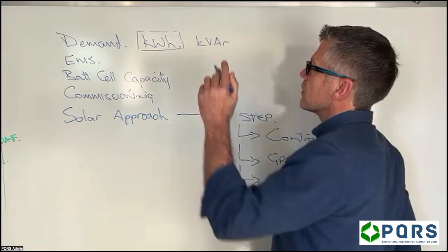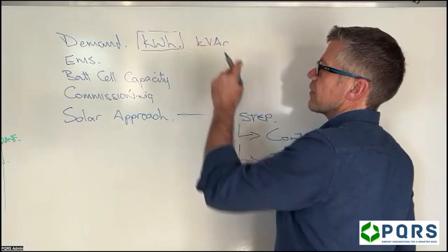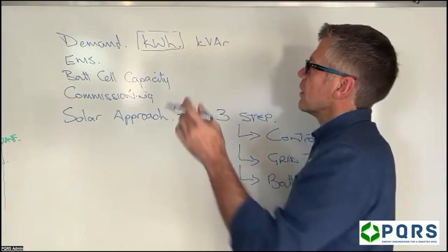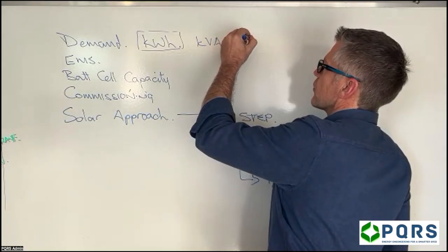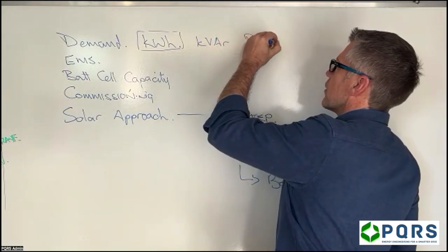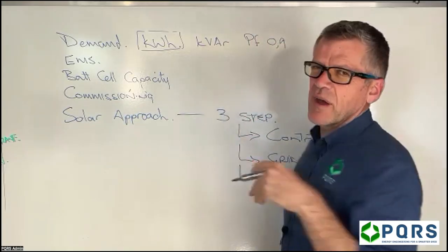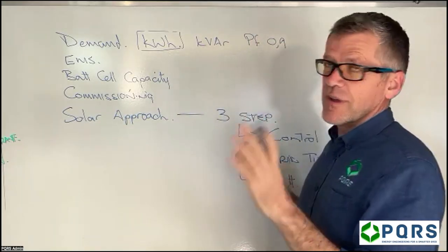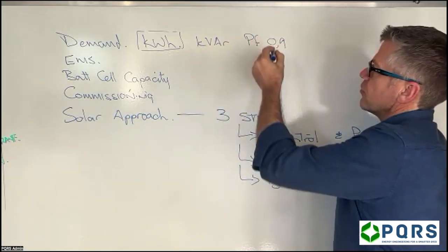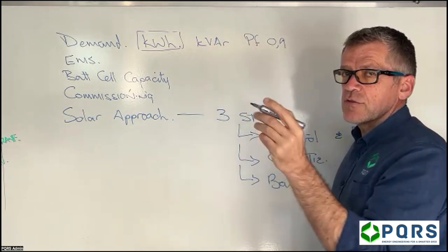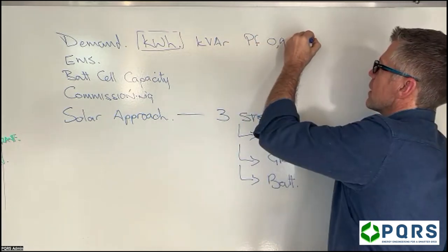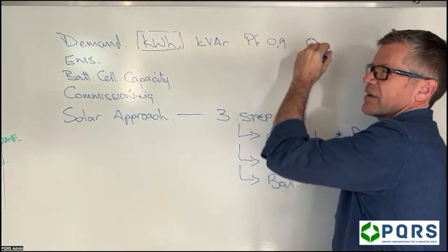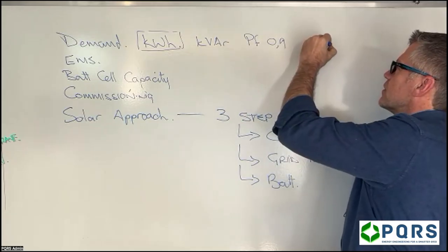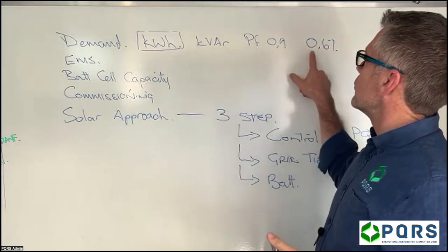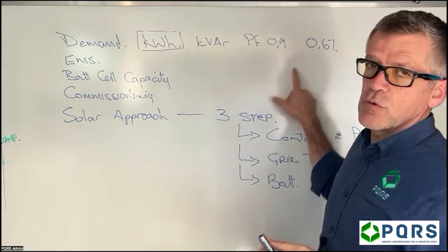The worst reactive power component I found is a concern, even though your bill shows a power factor of 0.9, 0.93, or 0.94, which looks impressive. But if you go through your installation, you'll see that over weekends the power factor can drop. The worst I saw was 0.67. This is going to negatively affect your installation.